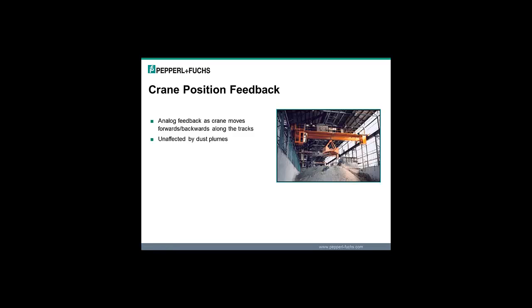Crane position feedback in these big open areas, like this particular crane is picking up rocks and dumping them, and you get giant plumes of dust that come up. In areas like that, if you want to position the crane as it moves back and forth, it is very difficult to do with a photo eye. The area is just way too dusty. So this is something, again, I think this application was solved with one of the F260 devices. But it just lets you know as the crane, you can do level control with it if you want to see if the levels of the aggregate below. But it's more for the cranes going forwards and backwards along those tracks as they pick up and dump off the crushed stones.